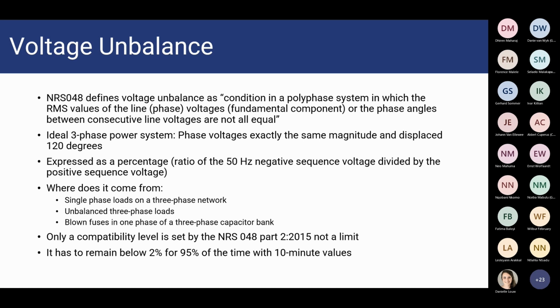Yeah, no, definitely. These are just examples of loads that can cause voltage unbalance on the network. But if you are supplied on a system where there is inherently voltage unbalance caused by some other loads further up in the network, or the system just doesn't supply balanced voltages, then yes, it's also voltage unbalance. Yeah, in this case, it was a solar farm, and one of the phases of the three-phase was lower than the rest. Yeah, no, that can definitely also be defined as a voltage unbalance.